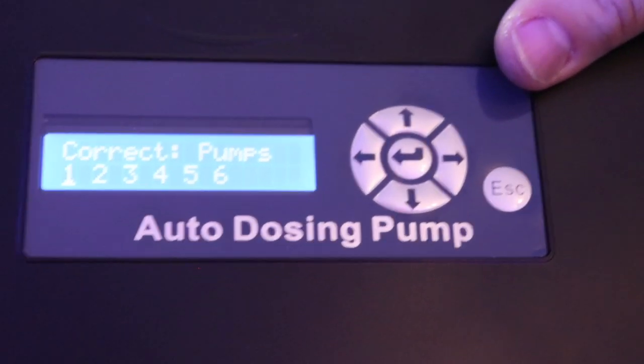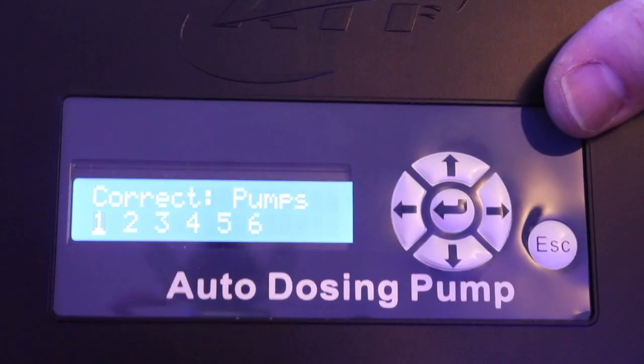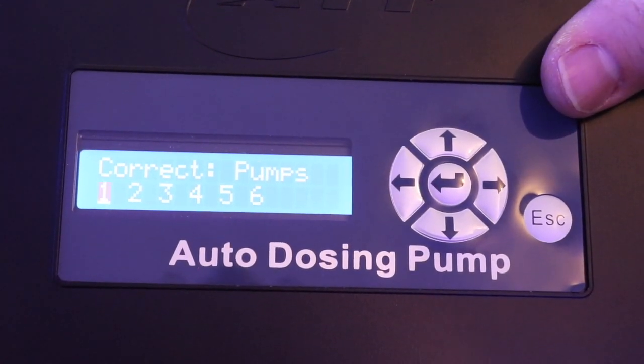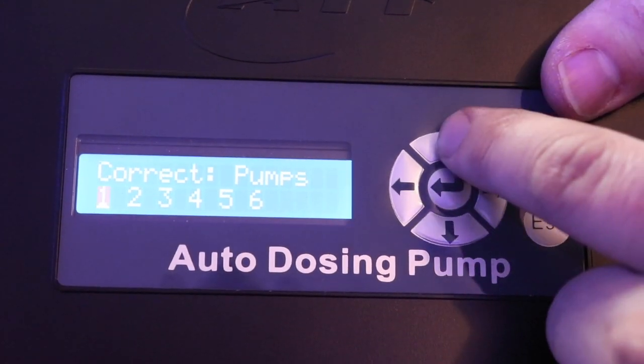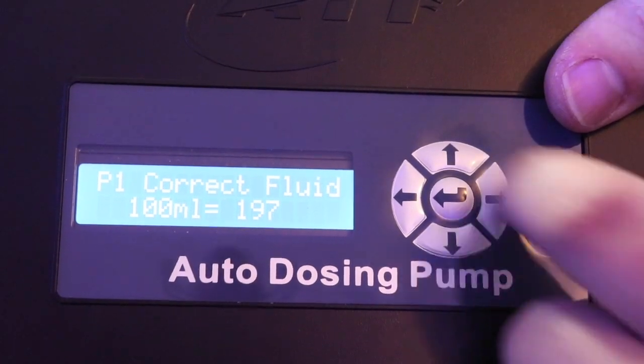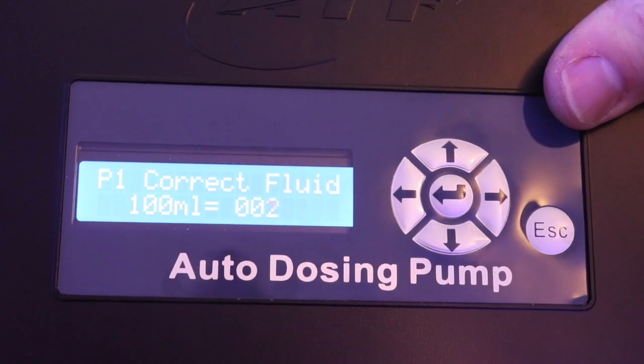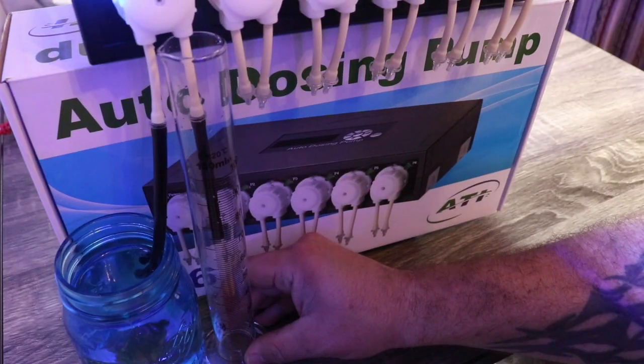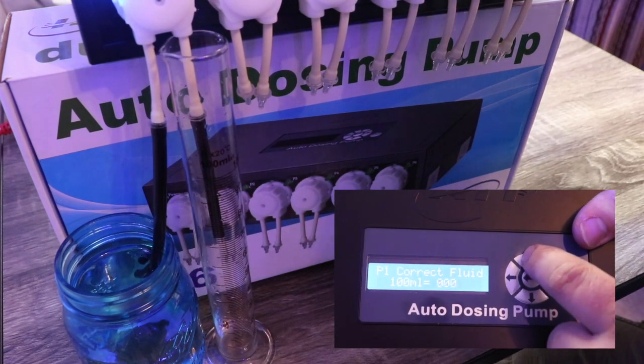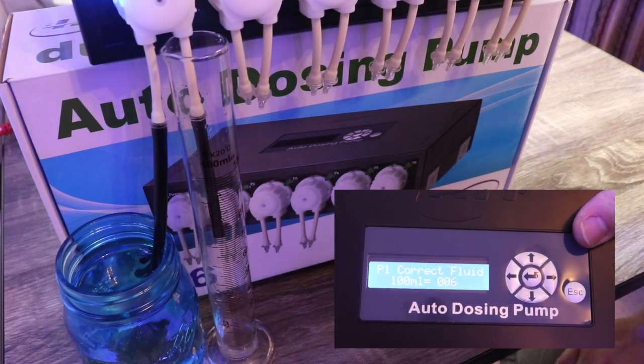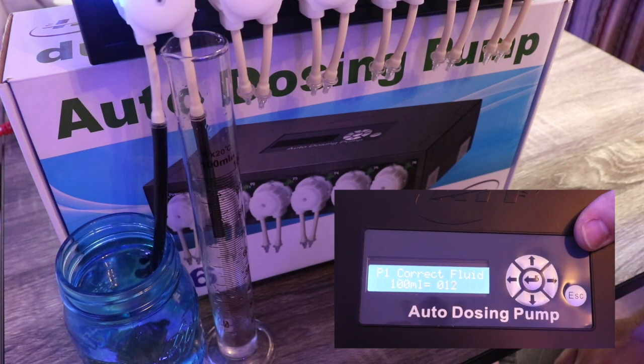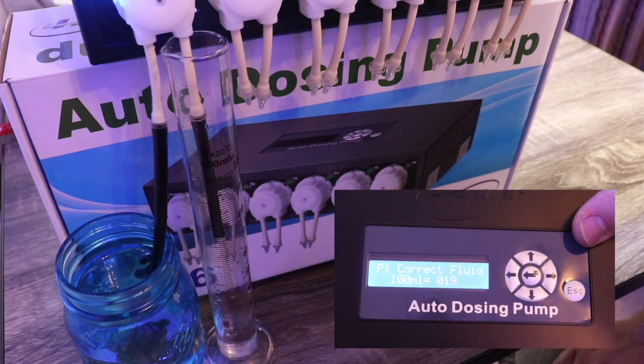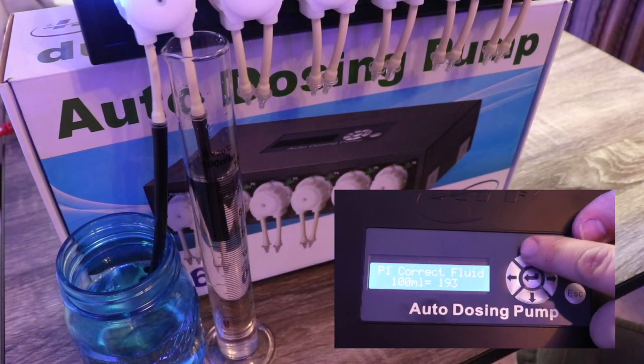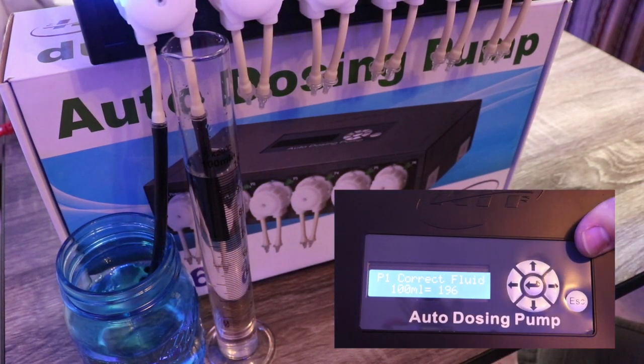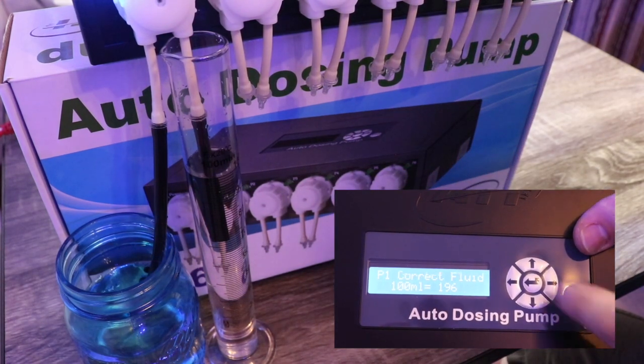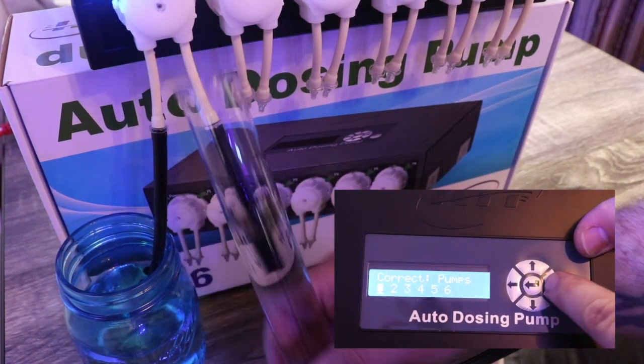Now, to get into calibration mode on your auto dosing pump, it's relatively easy. All you need to do is hit the up arrow once, and you'll see the screen pop up where it says correct pumps, numbering them 1 through 6 because those are your 6 pumps. And then once you select one of those pumps, go into it and then hit the up arrow again, the calibration is going to start. Once the fluid in the graduated cylinder reaches 100 milliliters, you hit the up arrow again and it's going to stop, and your auto dosing pump is now calibrated. That's all there is to it. All you need to do is repeat this process for each pump and you are ready to go.